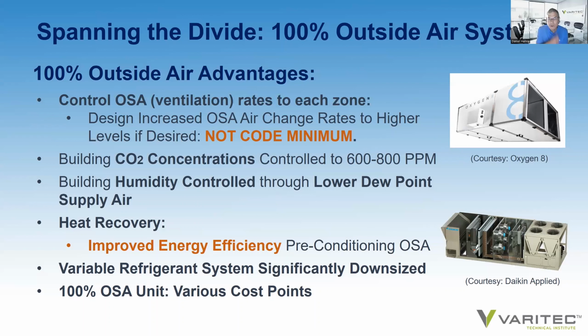You can provide deeper CO2 control. There's evidence that high concentrations of CO2 within a building might be a human health concern if you start seeing levels of 1,000 parts per million or above. So there's a current consideration and debate going on as to what those CO2 levels can be. But since the CO2 levels outdoor are below what they are indoors, we can help control CO2 levels more effectively. You can actually provide humidity control by providing lower dew point supply air. We can add enhanced system efficiency by incorporating the heat recovery solution that we discussed earlier. And in doing so, you can then downsize the variable refrigerant system that offers many various advantages.